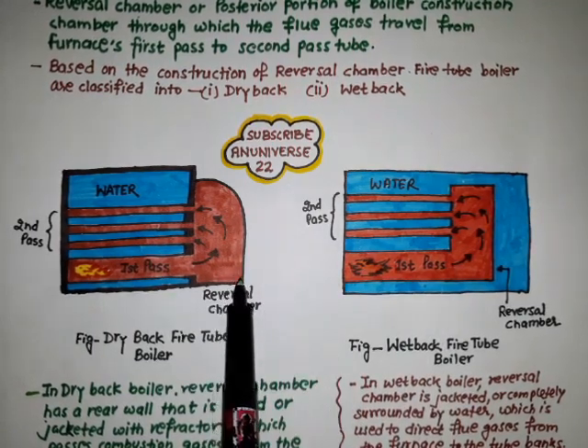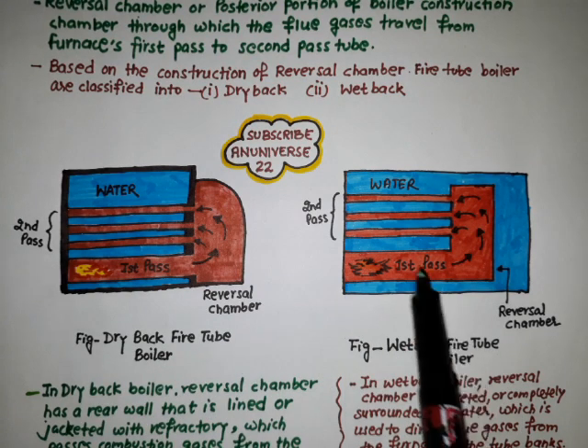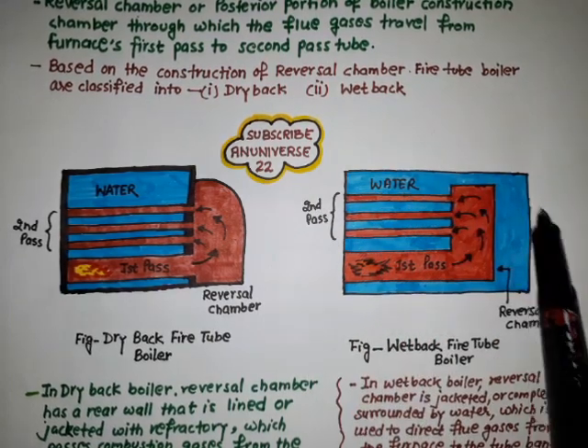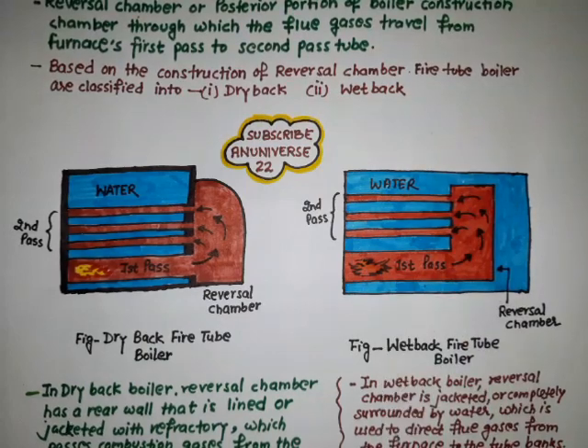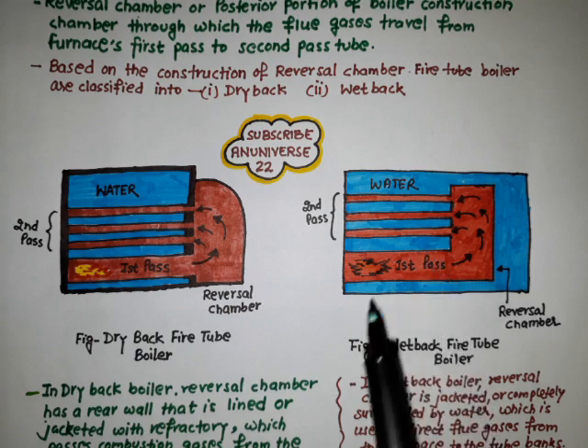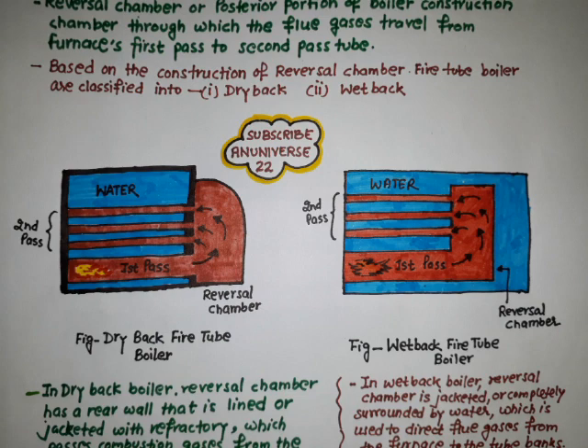Here we can see the key difference in the diagram: the reversal chamber is not surrounded by water in the dry back fire tube boiler, but in the wet back fire tube boiler the whole portion is surrounded by water. The blue color indicates the water surrounding all parts of the wet back fire tube boiler. The reversal chamber is completely surrounded by water and is used to direct flue gases from the furnace to the tube banks. The surrounding water absorbs the burner heat, helping to improve operating efficiency, as heat from combustion goes directly into evenly heating the water instead of the refractory.